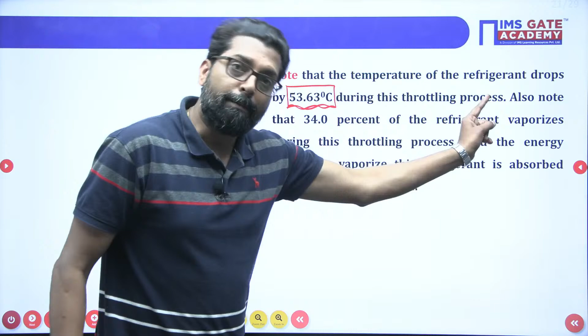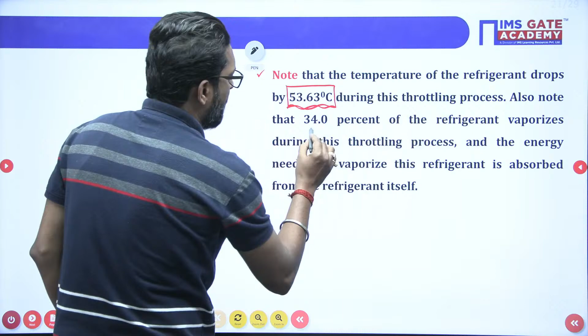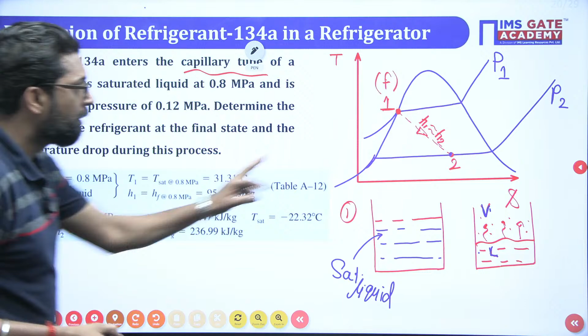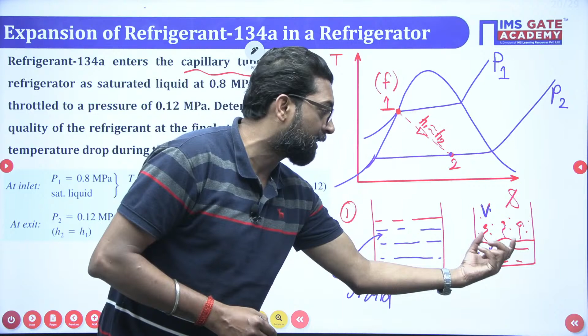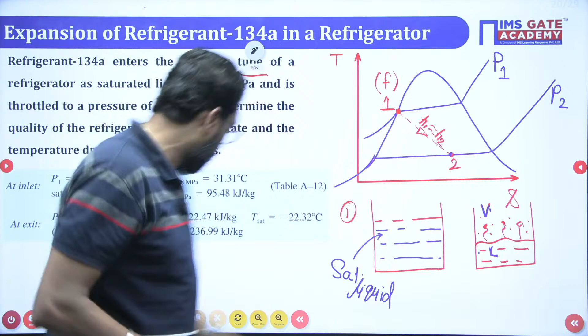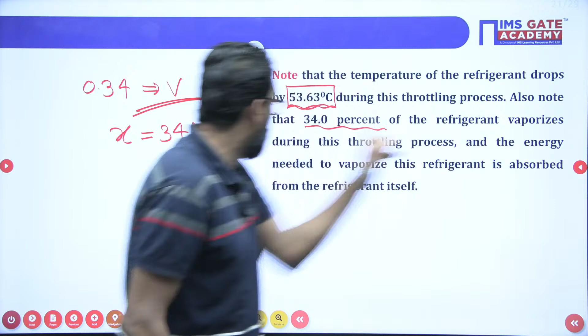During this throttling process, the temperature will drop. Why does the temperature drop? We already understand. Also note that 34% of the refrigerant will vaporize. Why? Because at point 2 there is liquid plus vapor. So approximately 34% is vapor. If you calculate the dryness fraction, that is your 34%. So 34% of the refrigerant vaporized during this throttling process.